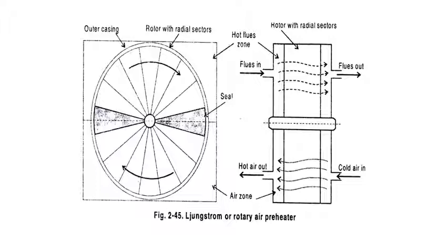We come to know whether there is a leakage in the air system or in the flue gas system. By close monitoring, one can examine whether leakage is happening. And of course, the sealings can be replaced during the annual shutdown. The gearbox rotates this at a very low speed, say 3 to 5 RPM.